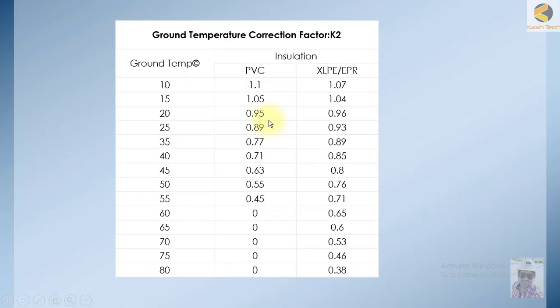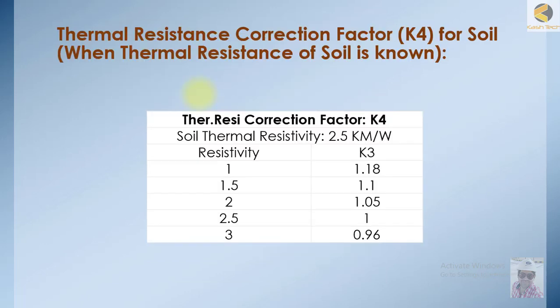Then we have the ground temperature correction factor K2. If the cable is in the ground, the derating factor is different. As the temperature increases, the derating factor is also decreasing. The heat dissipation in air is more compared to soil, so both have different rating factors.